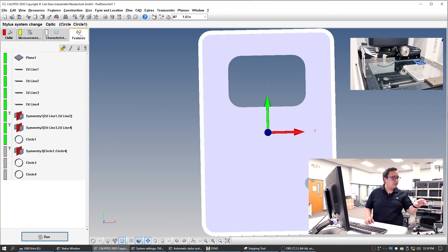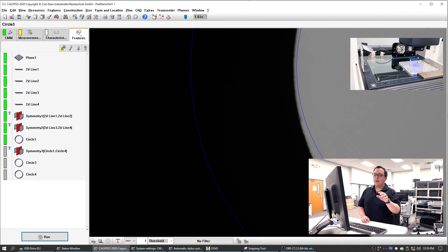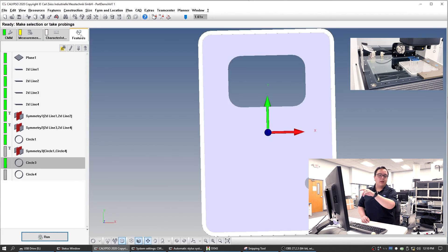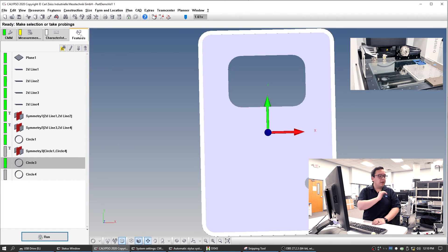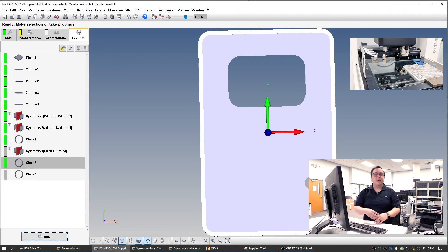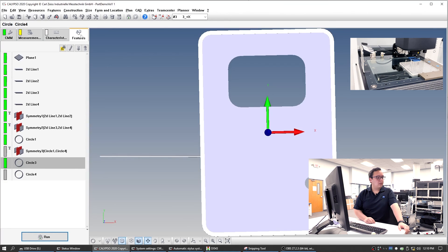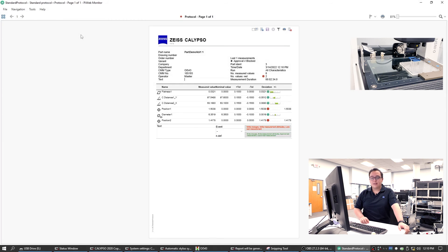It didn't do that second circle — here's why: it's actually going to switch to the camera and look at circle number three. The reason is when we were running this, we ran in the order of the feature list. So it did the plane first, running in that order. Now it's going to do circle number four because I programmed it last. If I wanted it to run before the camera, all I would do is drag it to run right before circle number three. So not to worry — we have a couple of opportunities here to optimize this and make it faster. In a couple minutes' time, we have a program that runs in about two and a half minutes.